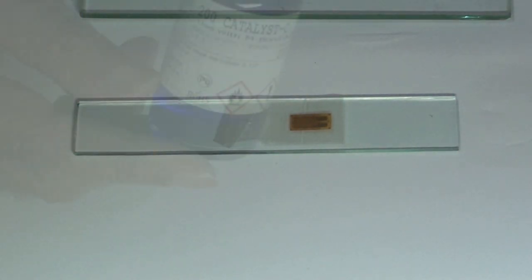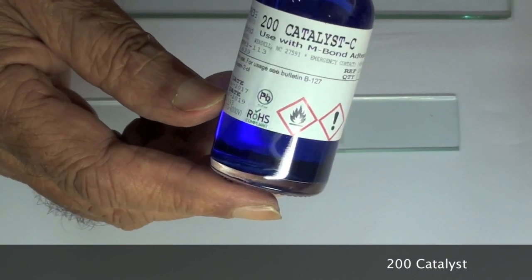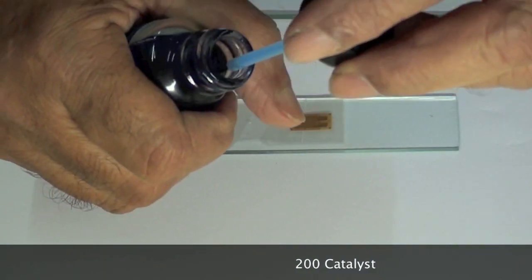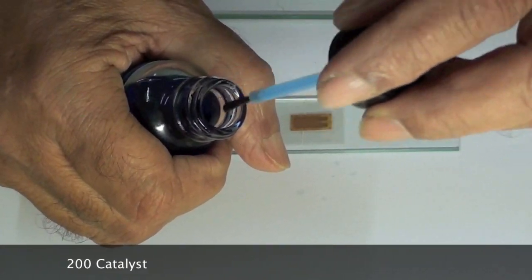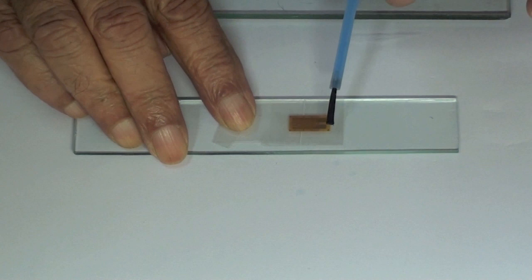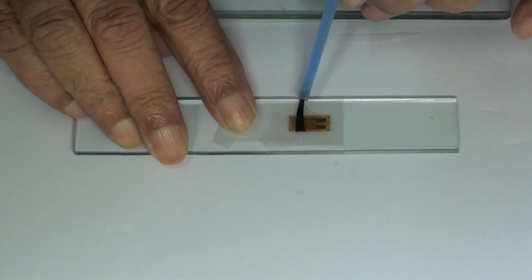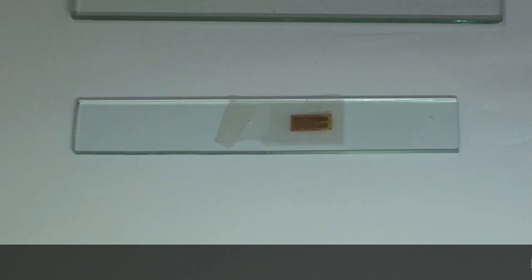Next, a very small amount of M-Bond 200 catalyst is applied to the bottom of the gauge. The brush is swiped against the bottle top several times to remove almost all of the catalyst. Then the bottom of the gauge is brushed just once. All the solvent in the catalyst should evaporate, which normally takes about a minute.